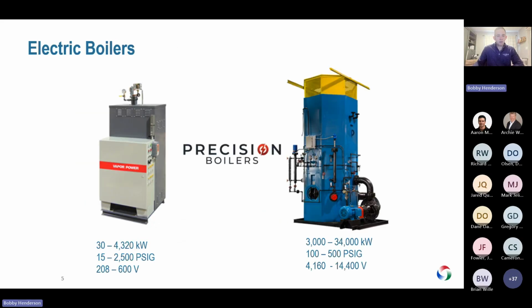All right, moving on to electric offerings. Precision boilers, we have a relationship with Precision Vapor Power, if you're familiar with them. They have anywhere from small electric resistance boilers all the way up to 480 volts here in the United States. And then if we get into the larger industrial steam applications, they have electrode boilers as well, going all the way up to 14,000 volts. So as you can see, wide variety of pressures available, steam pressures that we can operate. We also have electric hot water boilers with Precision if that's your need as well.